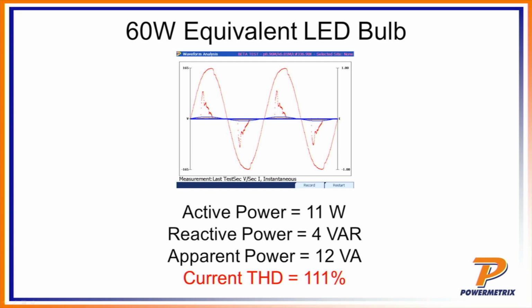If we look at the next example, which is an LED bulb. LED bulb uses even less active power. We're now down to 11 watts, and so that's only about 1/4 the energy that was being consumed by that 40-watt bulb. Reactive power, we're still generating 4 VARs for each and every bulb that we've got. Apparent power is 12 VA, and so once again, there's 1 extra VA being consumed by this bulb that most likely is not being measured by that watt-hour meter on the side of your building. And so what that means is that we've got a little bit of a loss once again.